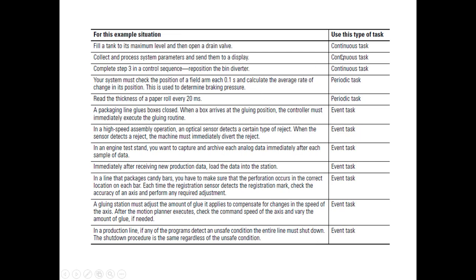Now that you've got that, here are some types of tasks you might want to use. You want to fill a tank to its maximum level and then drain — that's continuous, just ladder logic and there you go. For high-speed applications, a sensor detects a reject — when it detects it, you divert. Maybe you have a limit switch tied to an event; it would stop running the continuous task and run the event task to get a reject, then go back to continuous. These are some examples of periodic tasks — for instance, read once every 20 seconds on a timer: stop continuous, run this task, then keep going. Every 20 seconds the continuous stops, the periodic runs, then back to continuous.